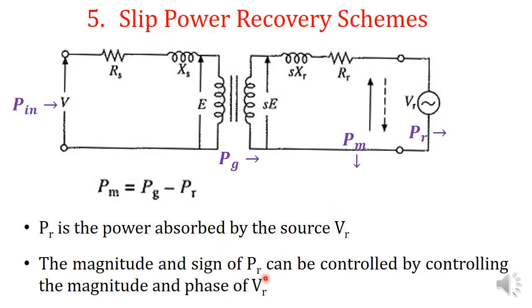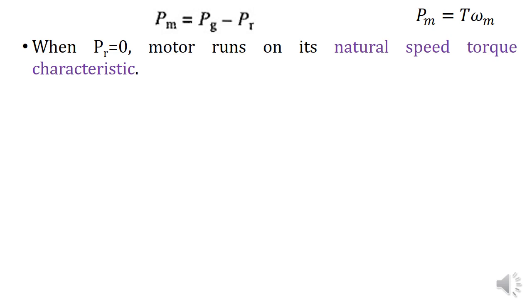The magnitude and sign of Pr can be controlled by controlling the magnitude and phase of Vr. By controlling the magnitude and phase of Vr we can control the magnitude and sign of Pr. We should keep in mind that Pr is the slip power in the rotor circuit, and by controlling the value of Pr we can control the speed of the induction motor.